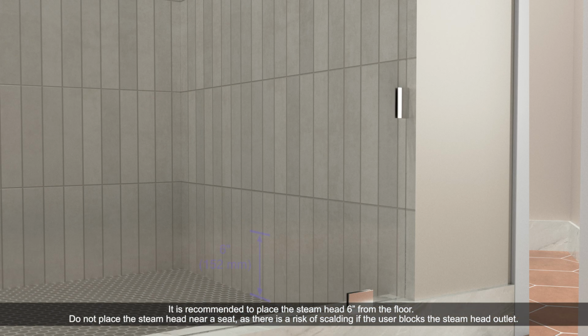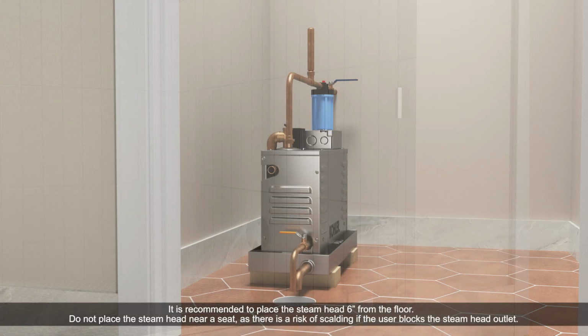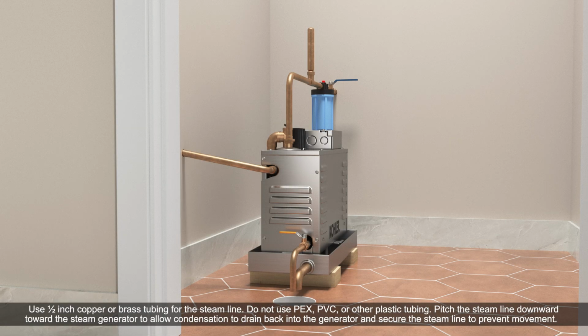It is recommended to place the steam head 6 inches from the floor. Do not place the steam head near a seat, as there is a risk of scalding if the user blocks the steam head outlet. Use 1/2 inch copper or brass tubing for the steam line. Do not use PEX, PVC, or other plastic tubing.